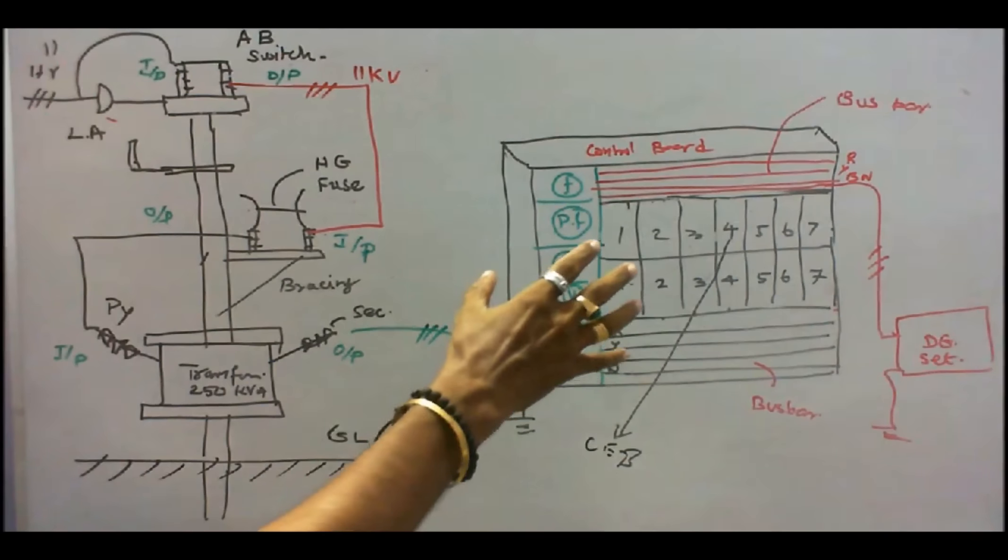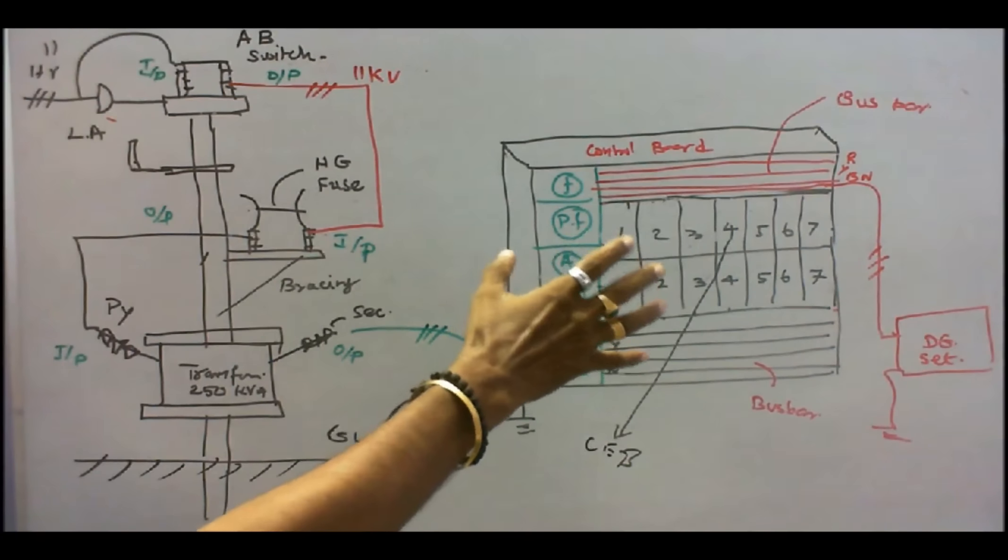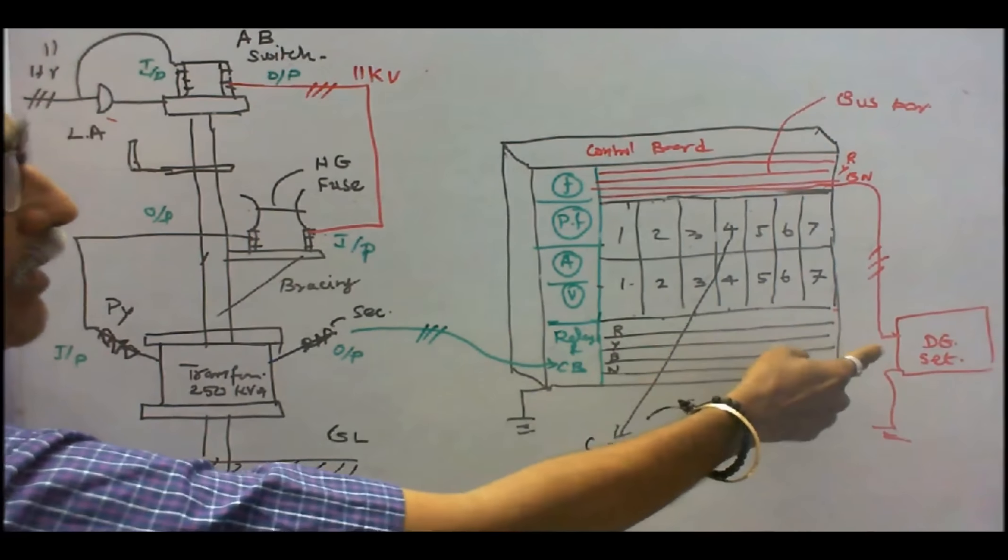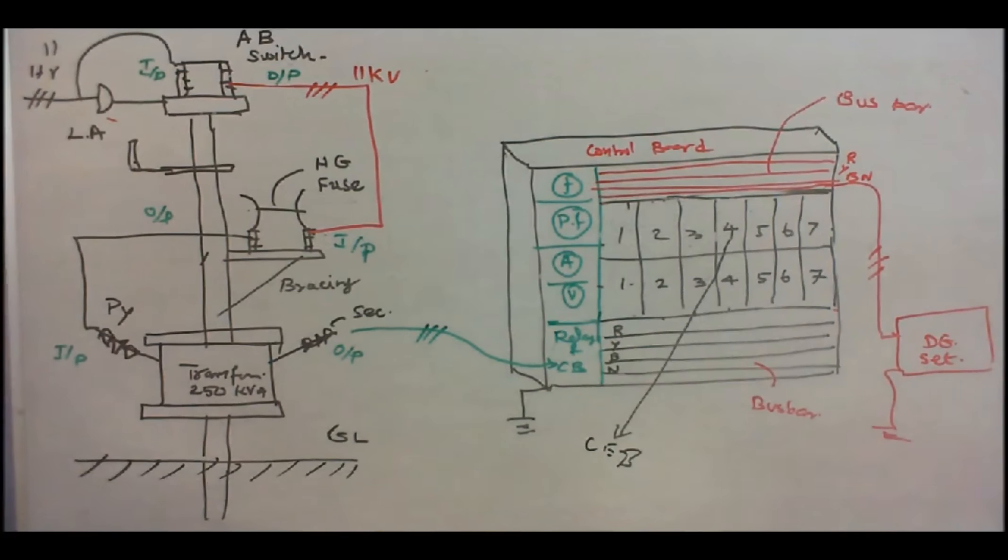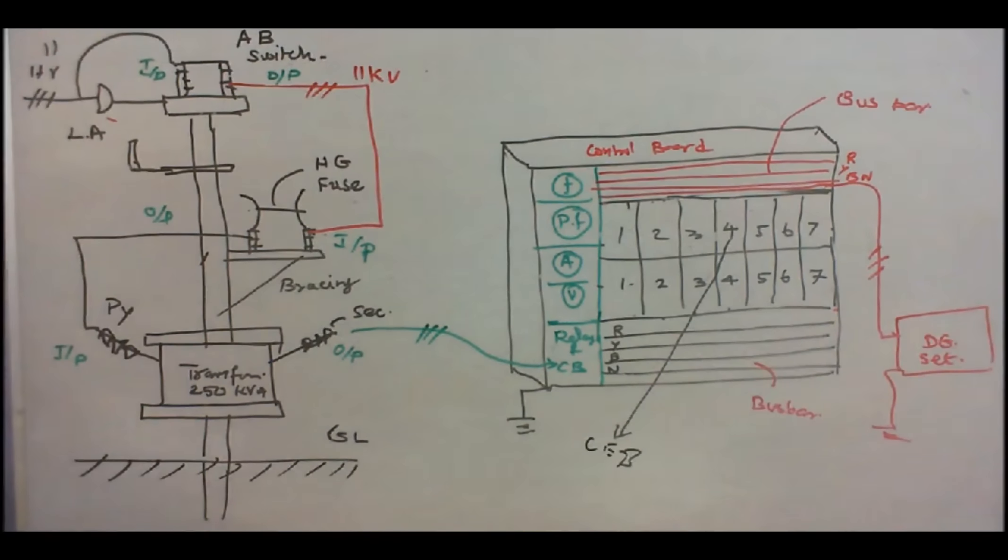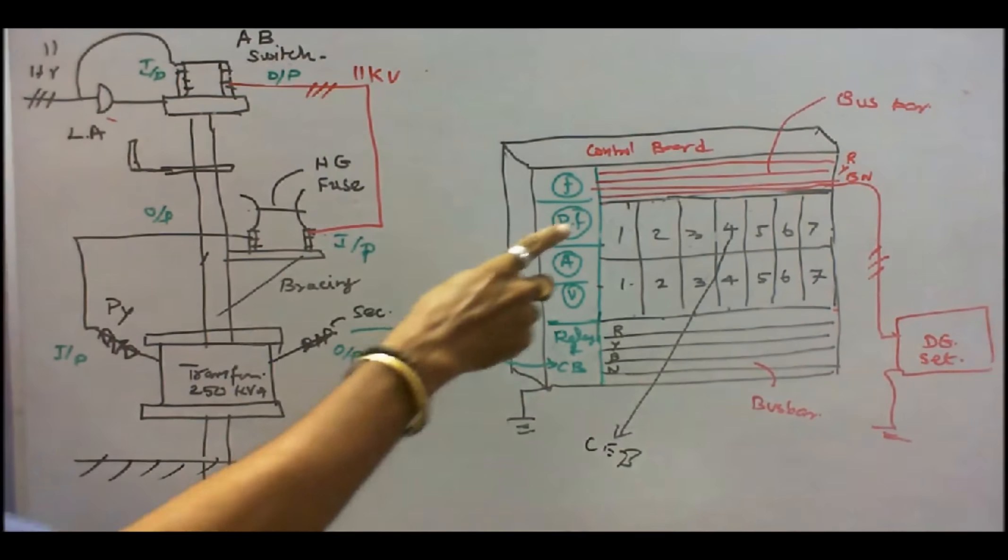This is a view of the main distribution control board. Here this is a TNEB unit supply. This is a diesel generator set supply. In event of power failure or maintenance, we have to operate the DG set. We have 7 feeders. Naturally we need 7 switches. Therefore totally we need 14 switches.